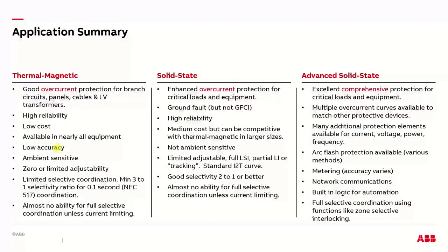I'll try to start wrapping it up here. Here's a summary of the applications. So thermomagnetic provides good protection for simple stuff: panels, cables, transformers. Very reliable, very low cost, sensitive to ambient, little adjustability, very hard to coordinate. And this is very hard to coordinate for this 0.1 second, which is the healthcare coordination code. That's way too deep to get into in this class.